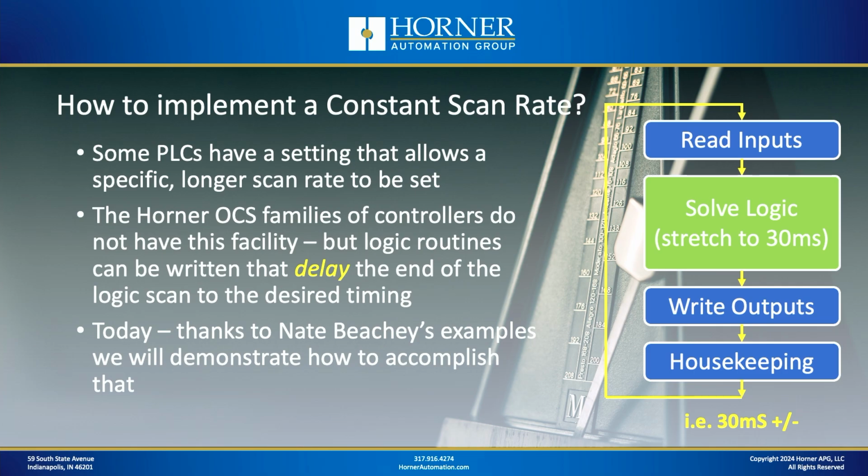Okay. So how are we actually going to accomplish that? Basically, we stretch out the logic portion of the scan to our target. If we're looking for about a 30 millisecond scan rate, instead of just letting our logic execute as fast as possible, we can add a little bit of logic to the end of our user logic that will stretch it out to a desired level. So what might have taken 2 or 3 milliseconds will now take about 30 milliseconds.